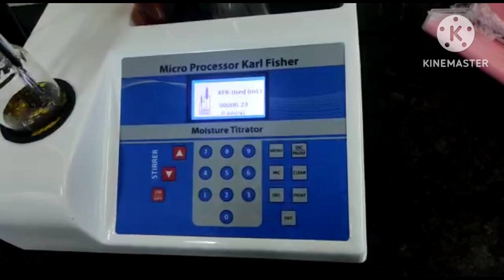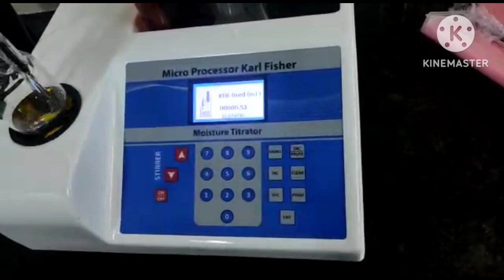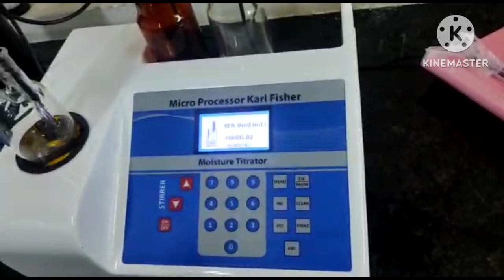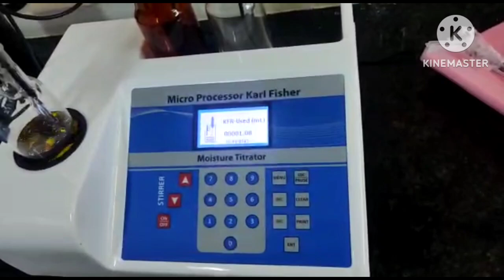Suppose if you have a sample which is moisture value less than 1%, then we have to take the sample amount in 5 ml or 5 grams. If the sample moisture content is more than 5%, then we have to take it in mg, milligrams, or microliter. So you have to remember that if moisture value is more, we have to take less sample. If the moisture value is less, then we have to take more sample.